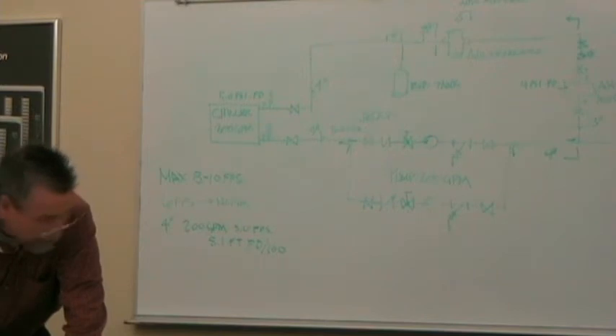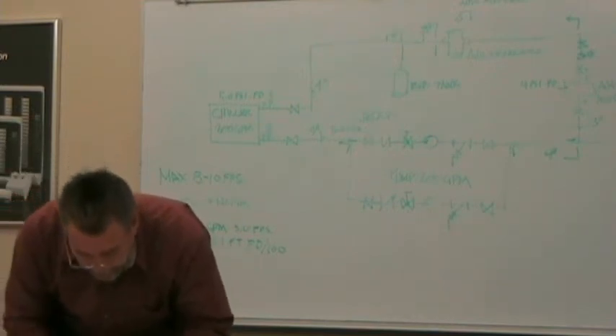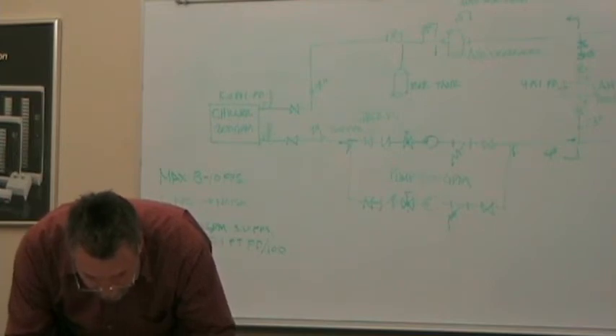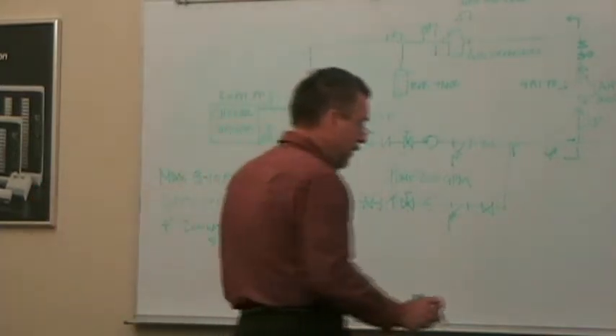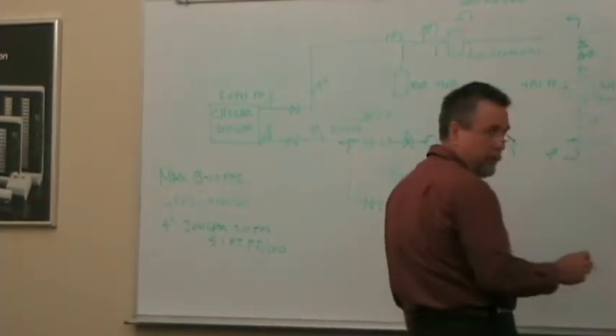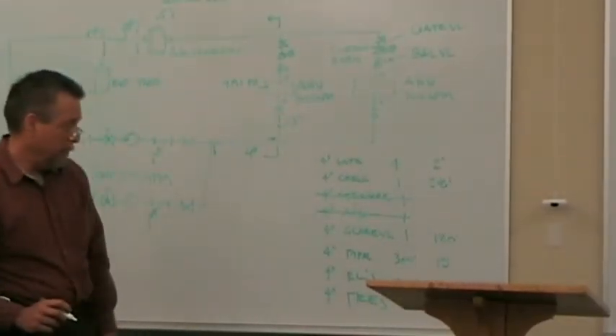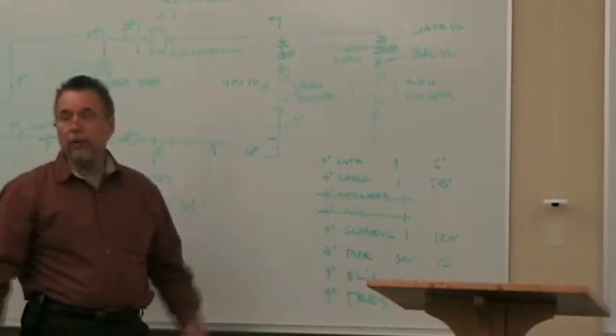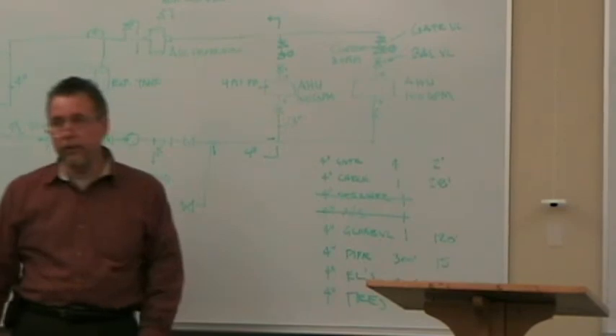Yeah. Elbows, we're talking about elbows. I'm going to use a standard elbow, not a long sweep elbow, but a standard elbow. In 4-inch pipe it is 12 feet. So I've got 20 of them, 20 times 12. 240. So all my elbows in that pipe amount to 240 feet of equivalent length of pipe. Each elbow is equivalent to 12 feet of pipe. So not too big a deal, but some amount of deal. And the last one is a T.